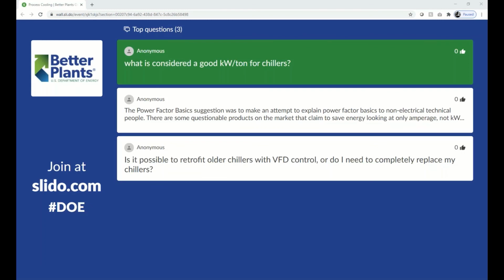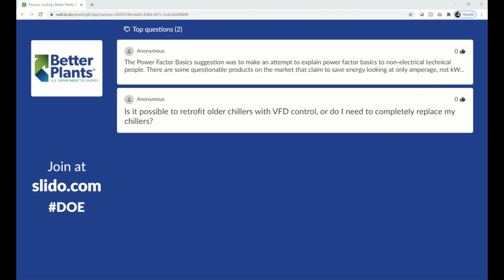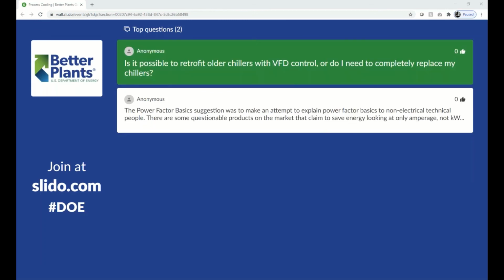Perfect. Thanks, Wei. Last question. Is it possible to retrofit older chillers with variable frequency drive controls, or do I need to completely replace my chillers? Here we have older chillers. I think for very old chillers, probably we cannot. There are some internal oil return mechanisms, so just putting a VFD on it probably won't work.